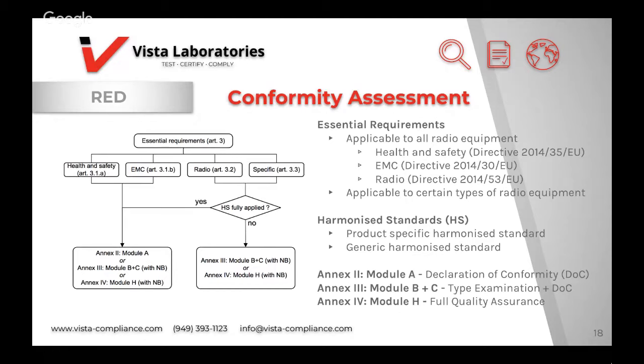So what are the annexes? Annex 2, 3, and 4 are different ways to show compliance with the essential requirements and different conformity assessment procedures. Annex 2 is the Declaration of Conformity, where the manufacturer is required to issue the DOC when the compliance of radio equipment with the applicable requirements of the RED has been demonstrated, and they declare that it's their sole responsibility, through their own internal production processes and control, that the radio equipment that will be placed on the market will satisfy these essential requirements. So it's a declaration of conformity by the manufacturer.